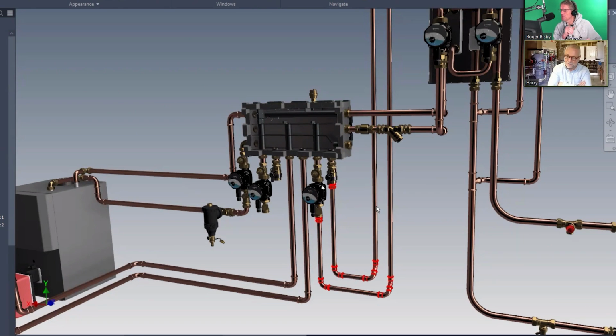That's just one of many systems you're working on. Like I say, the two jobs we just finished with two chemical plants, where the manifolds are about 2 meters long, 500 deep and 700 high, had two 650 kilowatt boiler houses in the same area, and then two 350 kilowatt heat pumps taking air to water up to 35, and another heat pump taking that water up to 70. It all ties together - we do hotels, houses, cottages, doesn't matter.